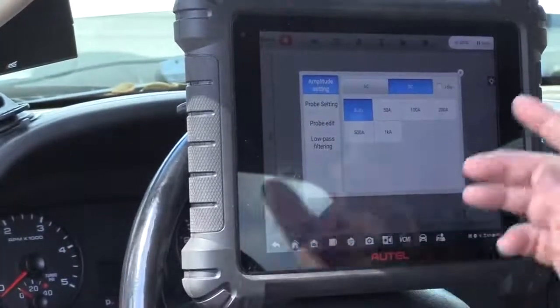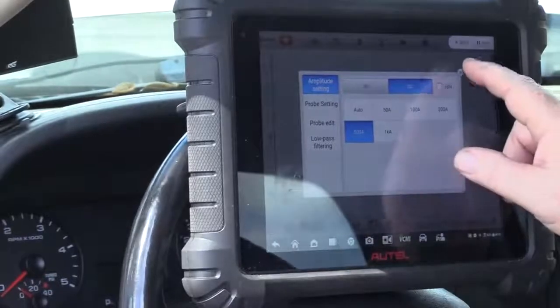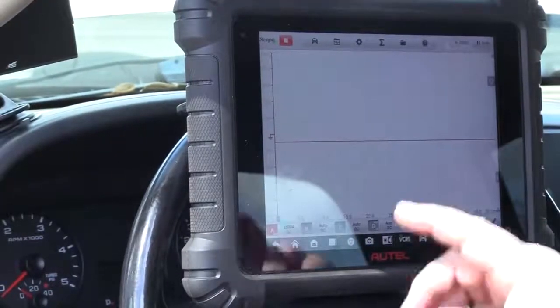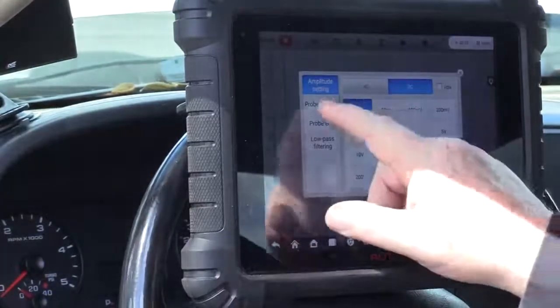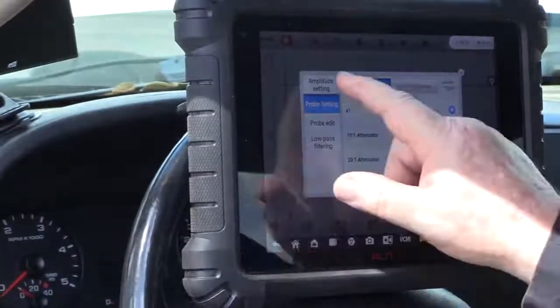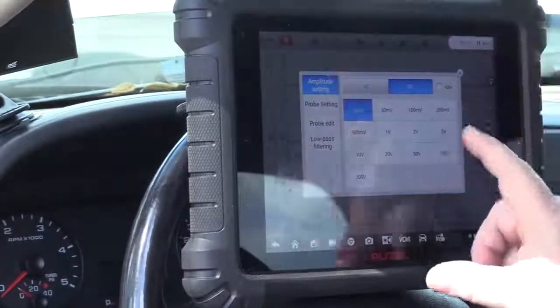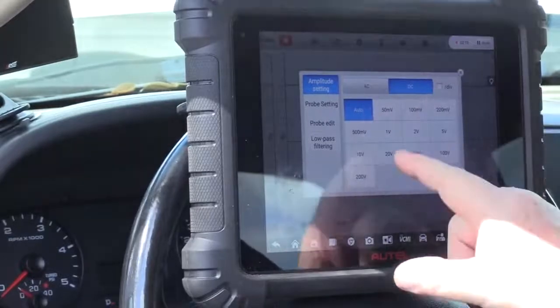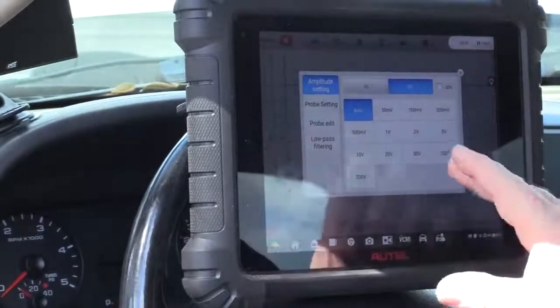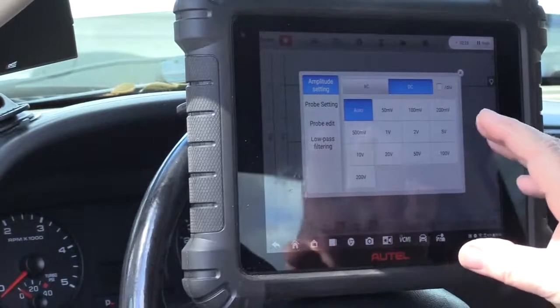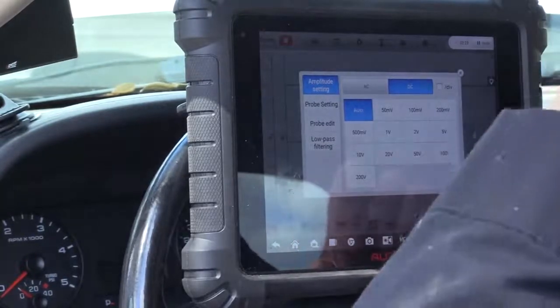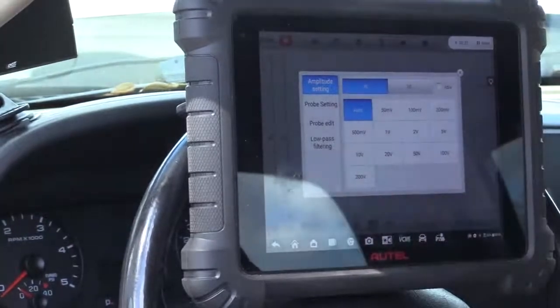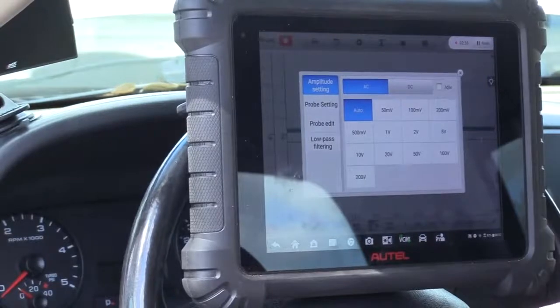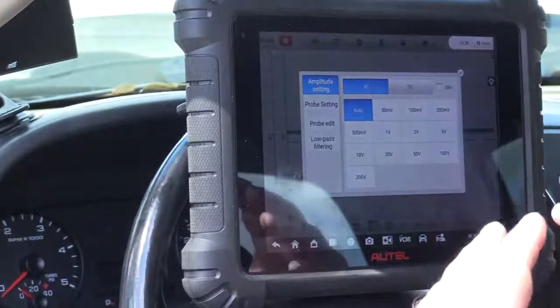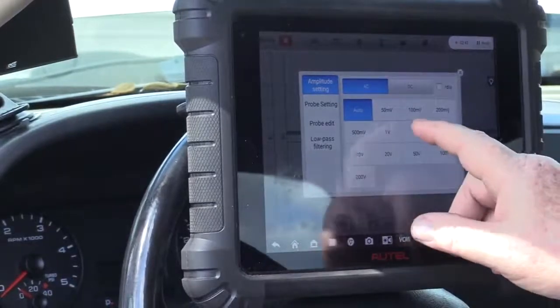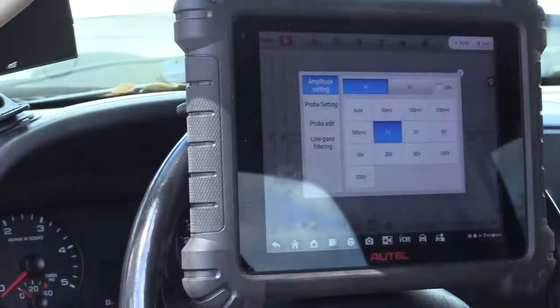Now we can go to the amplitude setting. Let's say we want to screen, say, 500 amps. We'll start with that. And now we're going to go on to the B channel. Again, this is a times 1, so that's okay. Amplitude setting. Here's where it's going to be a little different. You're used to me setting this to the 20 volt scale, but I'm not interested in the actual voltage reading. I'm interested in the change of reading. So I want to be able to see that easier by changing this to an AC coupling. That's going to take the DC component out of the signal and focus just on the change. So let's see what happens when we do a 1 volt scale, and we'll see what kind of change we get there.